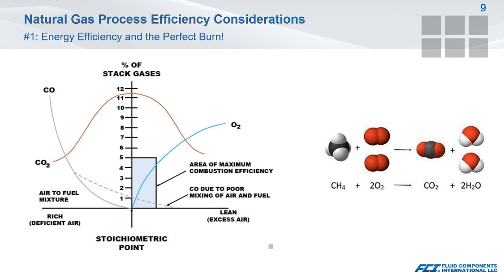Ideal operation occurs at the stoichiometric point, and the highest efficiency occurs in the blue zone to the right. Operation to the left of the stoichiometric point results in incomplete gas combustion and production of carbon monoxide, with a greatly lowered efficiency and presence of unburned gas in the flue gas. Operation to the right results in excess air, which is heated by the flame and carried out in the flue gas, resulting in efficiency loss. The excess oxygen also results in an increase in NOx production. Mass flow measurement of both the natural gas and air feeds will account for changes in gas pressures and temperatures not accounted for in pure volumetric measurements, allowing you to better keep your efficiencies within the blue zone.